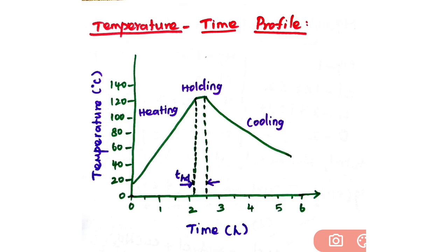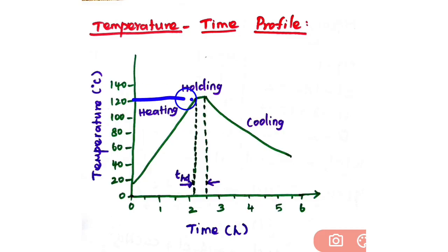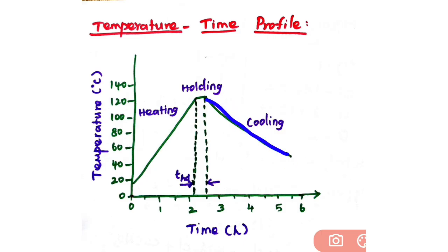This is the temperature-time profile for batch heat sterilization. Raising the temperature of the medium in large fermenters can take a considerable period of time, depending upon the rate of heat transfer from the steam or electrical element to the medium. There are three periods: the heating period, the holding time, and the cooling period. Once the sterilization temperature of 121°C is reached, the temperature is held constant for a particular period known as the holding time.